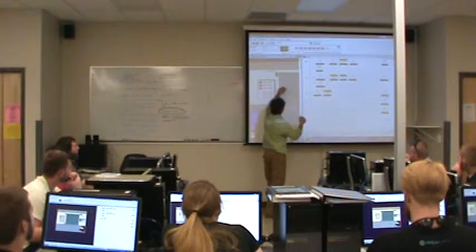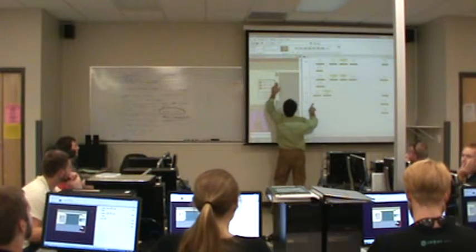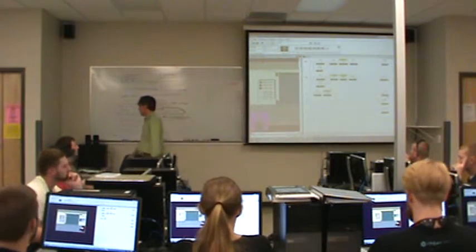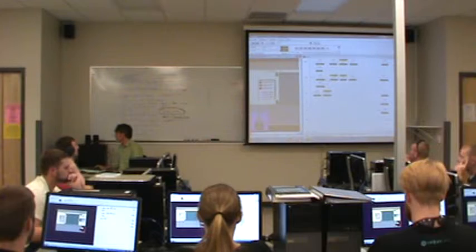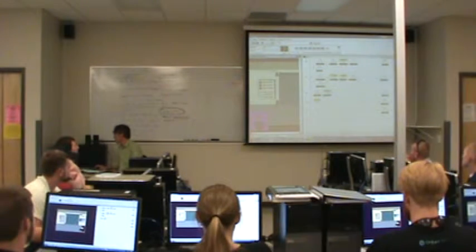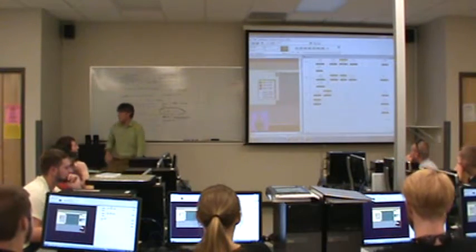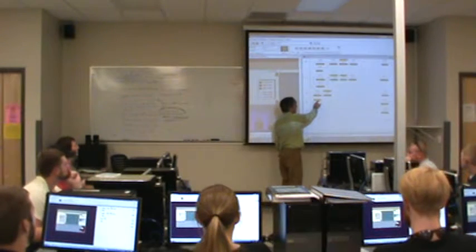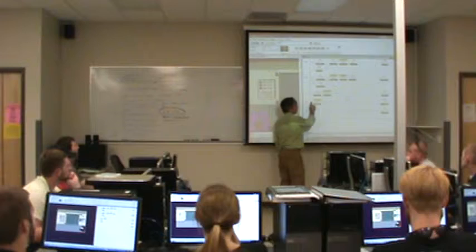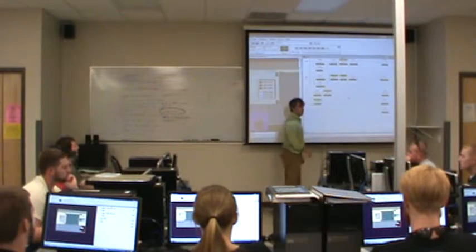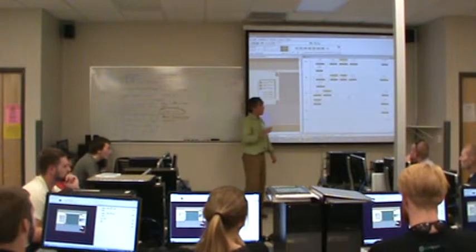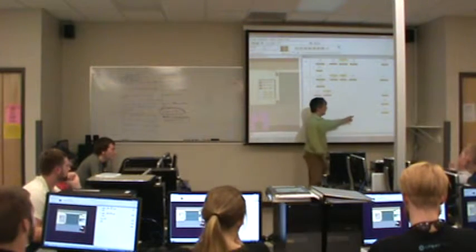I just remember what they mean. Okay. So I'm going to take a set of contacts like that, but I'm going to use this address for the open lamp. So what this will do is when the upper limit switch is not made, I will have a 0 on bit 3. That 0 will be inverted to a 1, and the open lamp will come on. That's really the only condition for the open lamp being on, is that upper limit switch. On the other hand, the only condition for the shut lamp is what?